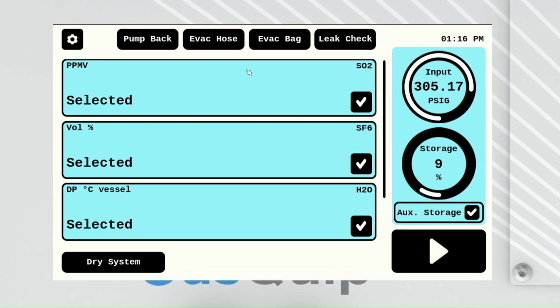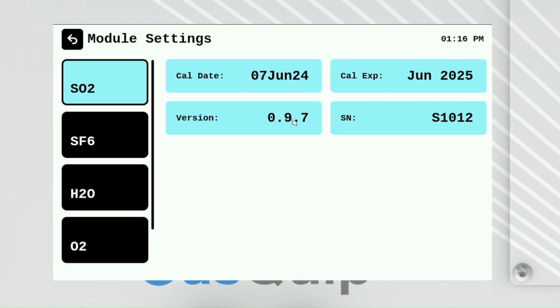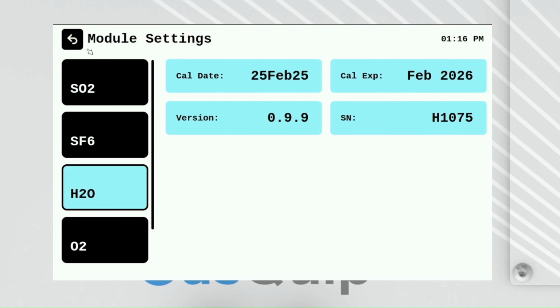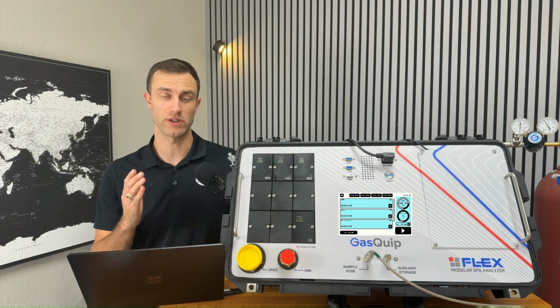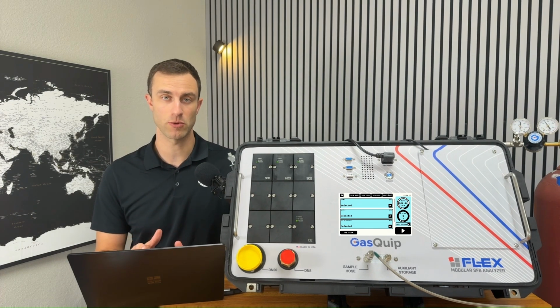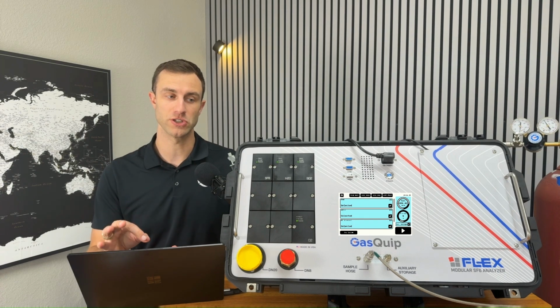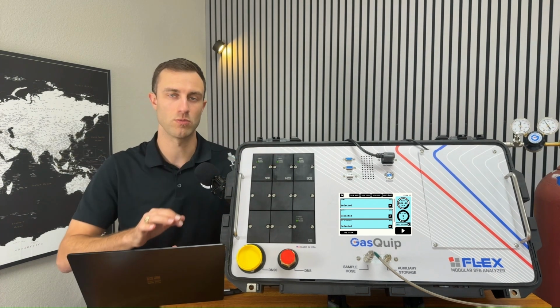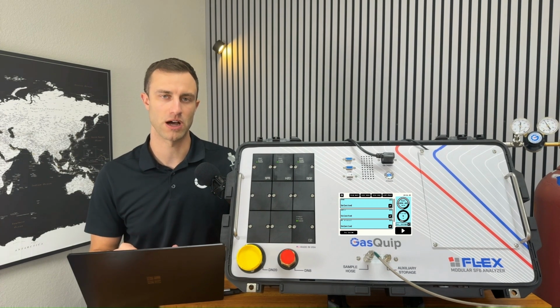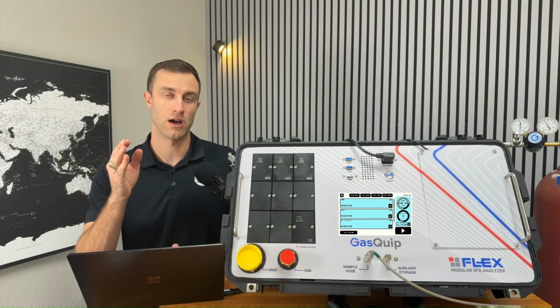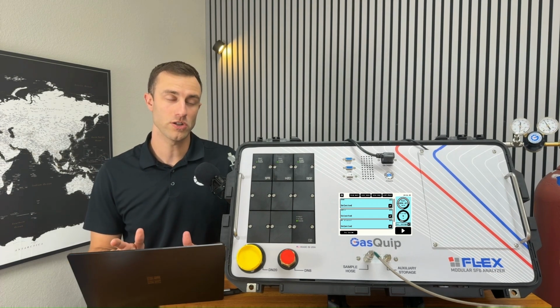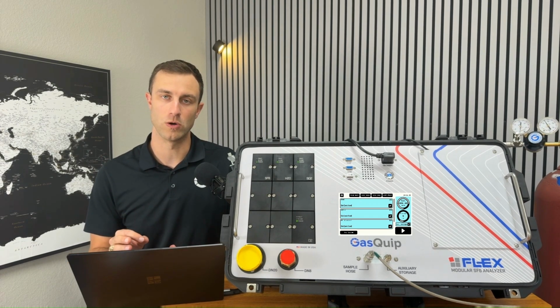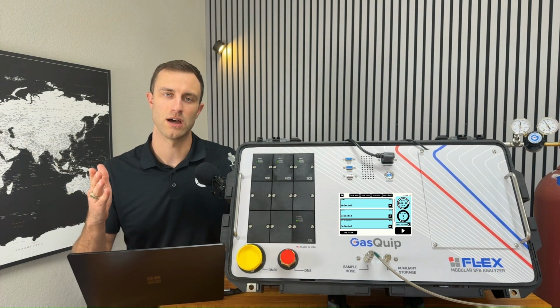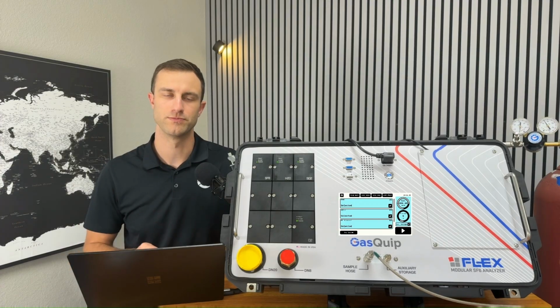Going back to the analyzer close-up, we now see our H2O sensor installed here, and it automatically shows up in our module settings with the correct information. If you're able to, you can share your email address with us. We have an automated system that we put together that will send you a notification about a month before each of the individual modules is due for calibration or calibrated module replacement. And it'll send you one on the day that is actually due. And it will also include a pre-generated quote to make this process very simple to keep your analyzer up to date and calibrated.